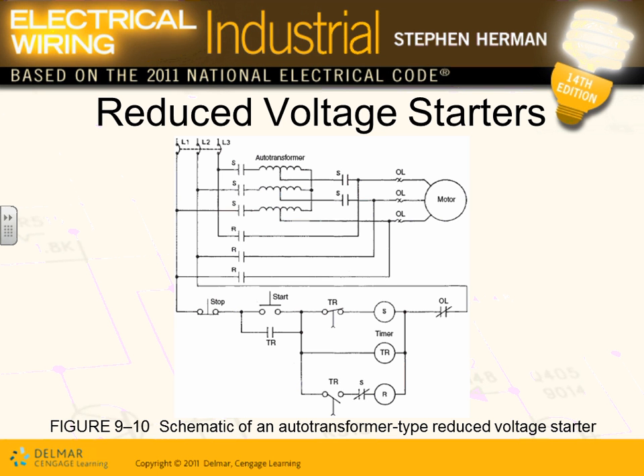So these two, when they close, they energize this. This will continue to energize. So when the timer times out, this will isolate 1, 2, 3. Now this will continue to have some power. I see your point. This one continues to have some juice up to this. So if you want to fully isolate it, you probably need another contact right in here. Another contact. Does ours in the book have that? No, they all have. I see your point.